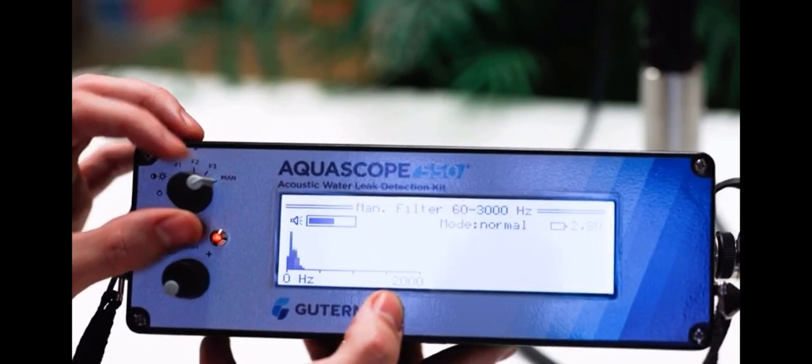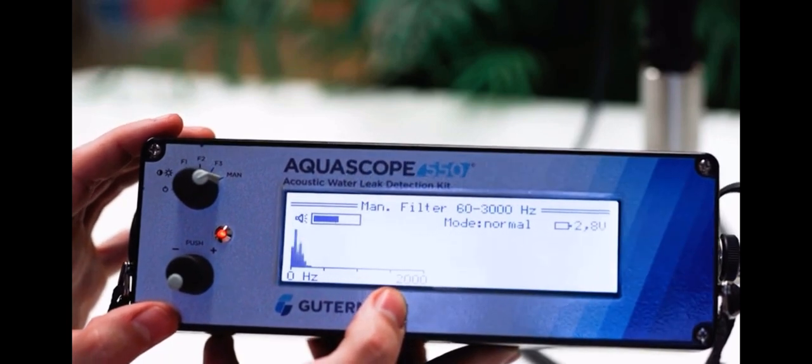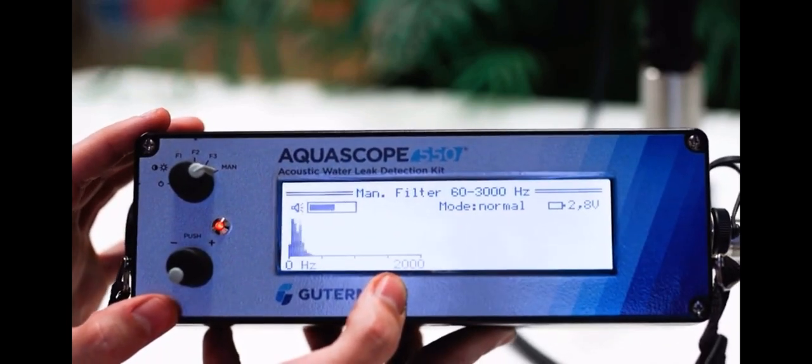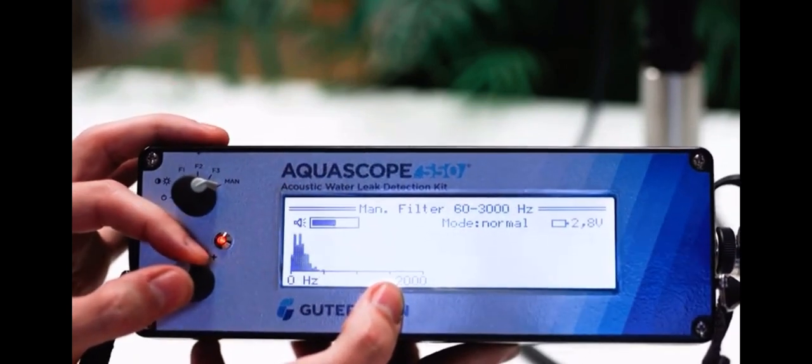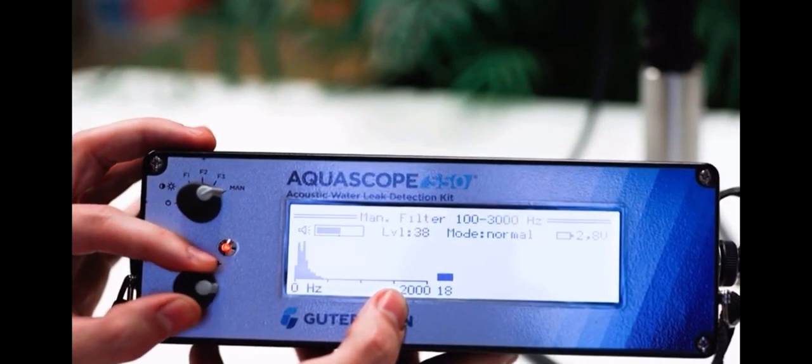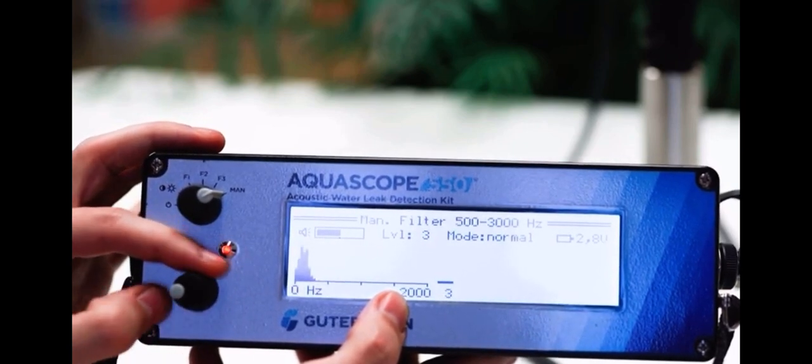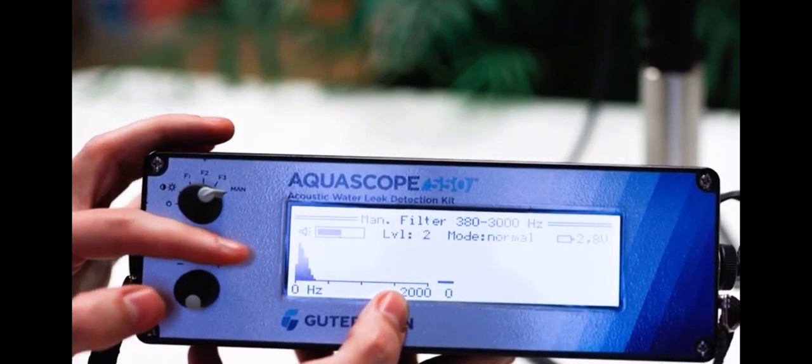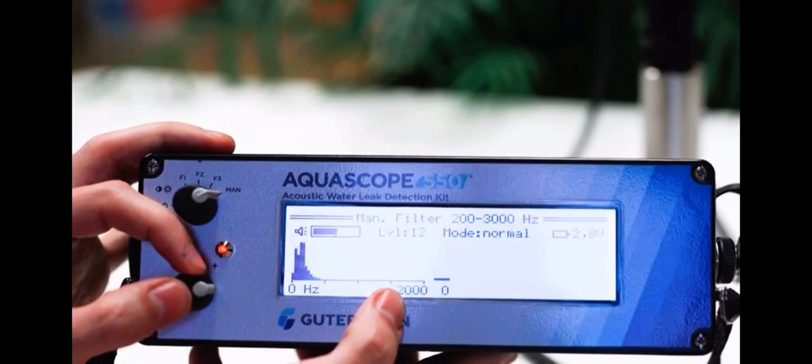Access the manual filter mode by rotating the top dial all the way to the right. On this screen, you can manually set the lowest and highest frequency of captured sound, as well as use frequency shifting to boost audible low-frequency noise, such as noise created by leaks on plastic pipe, into the range for human hearing.